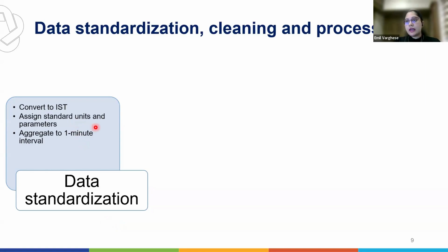And then there comes the standardization of units. Sometimes your reference instruments are recording in ppb, while your sensor is giving micrograms per meter cube. Now, if you want to compare your sensor to your reference instrument, then definitely at this stage you have to convert the units. This becomes an important thing because sometimes you have CO values in milligrams per meter cube on one side, and on the other side your reference instrument is recording in ppm. So this needs to be carefully done.